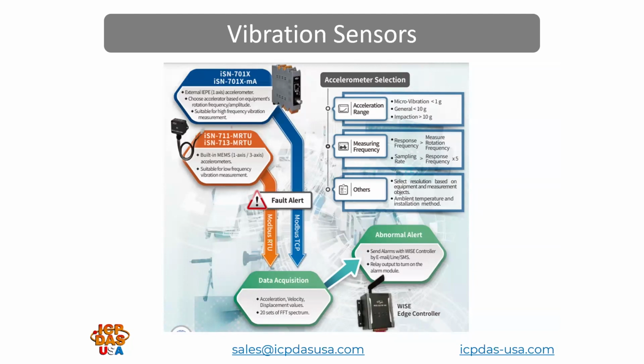The ISN 700 sensors can be connected to a monitoring system and upload real-time data. Engineers can analyze the vibration data remotely to find out which equipment has reduced production yield or even might have the possibility of downtime. This will bring a more stable manufacturing environment to the users. The ISN 700 provides IEPE and MEMS accelerometer measurement. It supports Modbus TCP and Modbus RTU protocol to read acceleration, velocity, displacement, and fast Fourier transforms or FFT spectrum values.